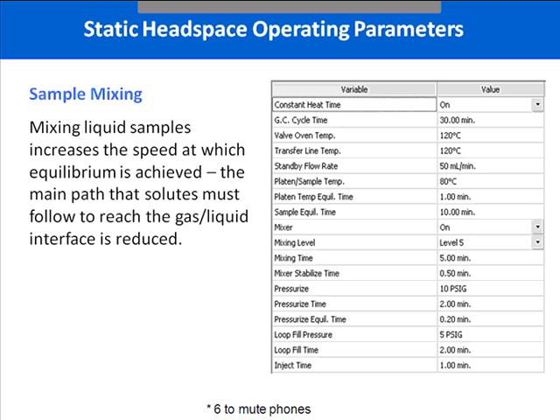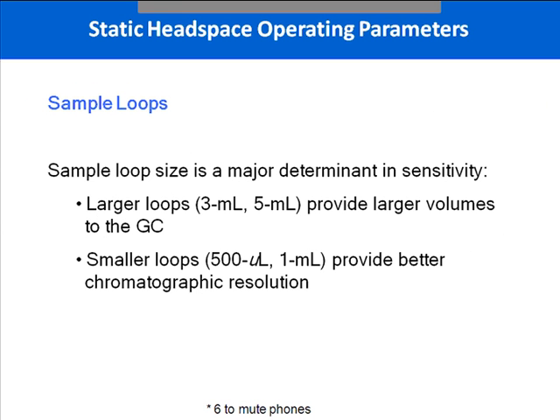Sample mixing is a parameter available to assist you with troublesome matrices. The HT3 offers various mixing levels and speeds using the OptiMix system, which allows for varying power settings from 1 to 10. By optimizing the sample mixing time and level, you can increase the amount of target analytes going into the headspace. In terms of sample loops used in headspace analyzers, you have to balance the factors described. The best way to determine the optimum loop fill time is to attach a flow meter to the vent and monitor the flow. The HT3 ships with a 1 mL sample loop that is common for many types of static applications.